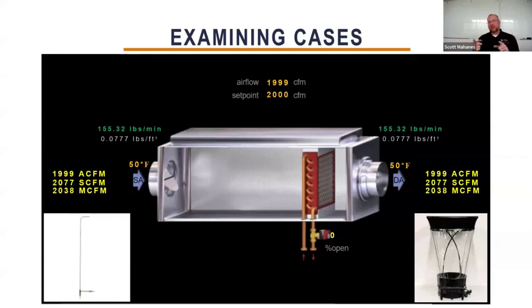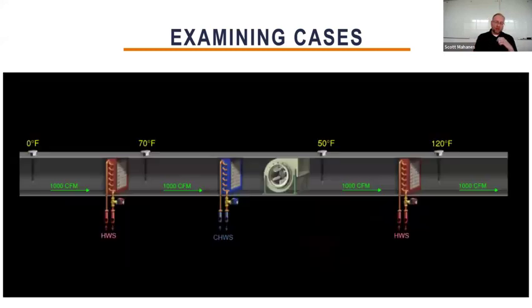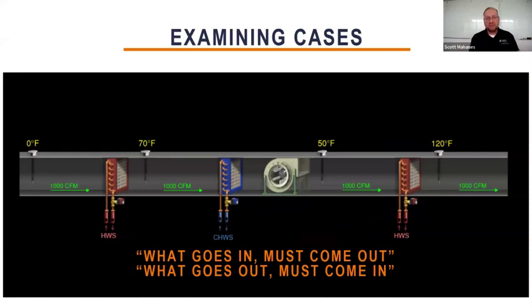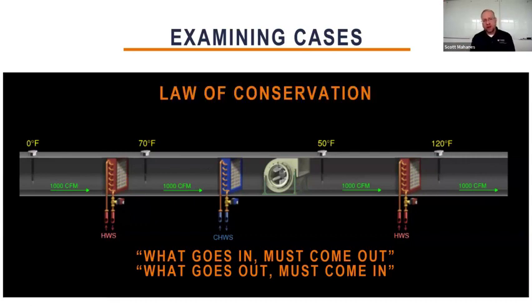What's interesting about this example is that I'm going to change this to a different scenario. There's this adage we believe in: what goes in must come out, and what goes out must come in. And we believe that if we measure 1,000 CFM over here, again presuming there's no leakage or additional airflow source, that 1,000 CFM is equatable or can be allocated to every section of this air handler. So we might measure 1,000 CFM in volume here and say, well, there's a flow station right here, and I can calibrate it with this measurement. And so we'll calibrate the flow station with 1,000 CFM. We believe in this adage that I can do that because of what goes in must come out. Well, I learned a year ago that this is really called the law of conservation, and we're utilizing the continuity equation to do this.